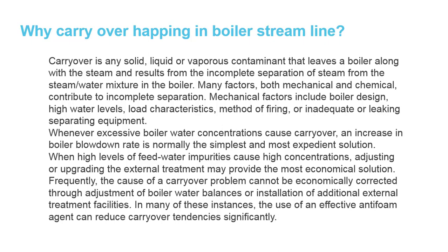Frequently, the causes of a carryover problem cannot be economically corrected through the adjustment of boiler water balances or installation of additional external treatment facilities. In many of these instances, the use of an effective anti-foam agent can reduce the carryover tendency significantly.